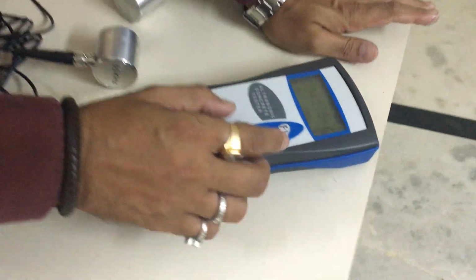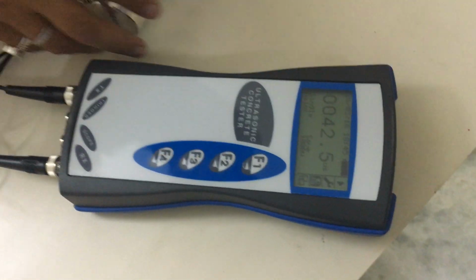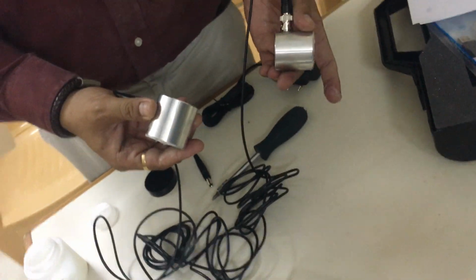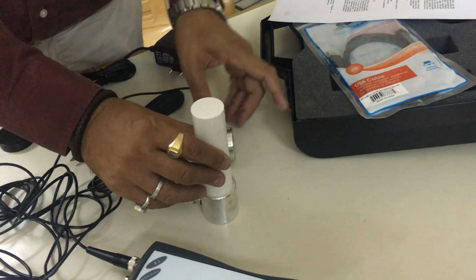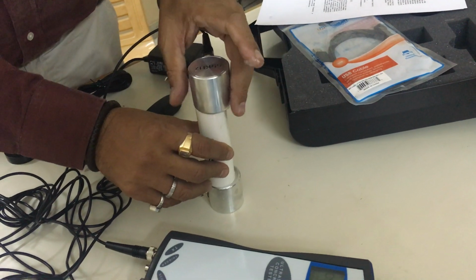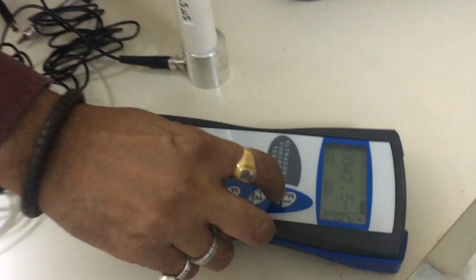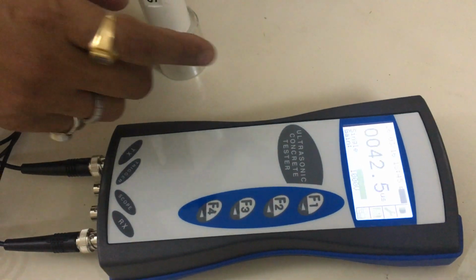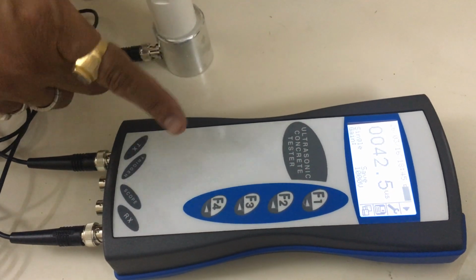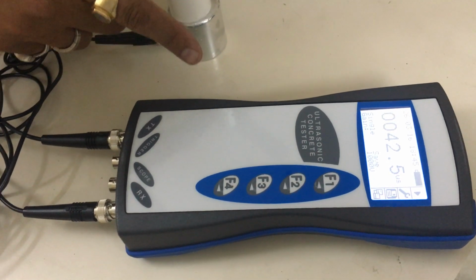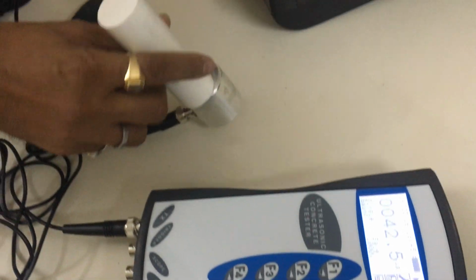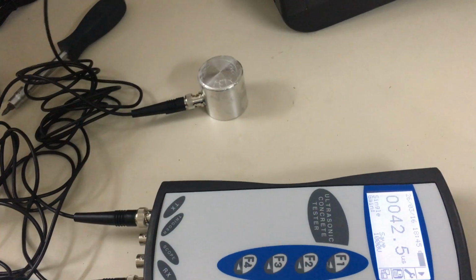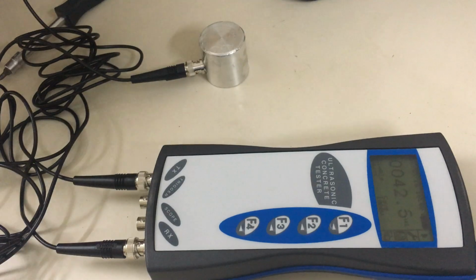So far I have explained what it does. You have a 55 kilohertz probe, and I have a calibrated sample of 42.5. Every time I check this for its value, 42.5 microseconds, by pressing the F1 key, then I am sure that my instrument is measuring correctly and is ready to take any test. So with this you can go and take the test.